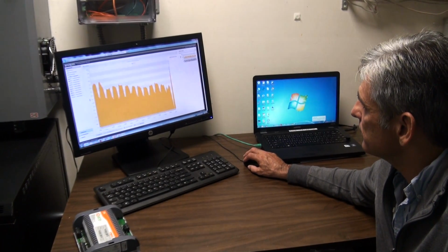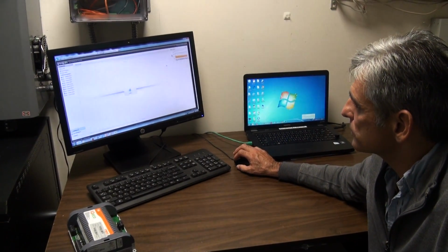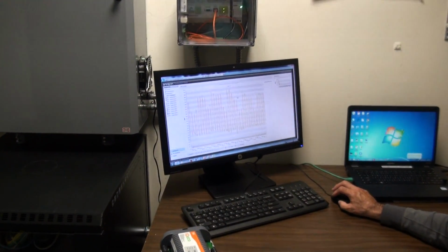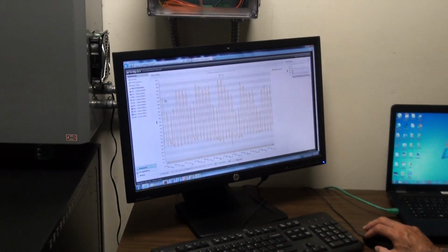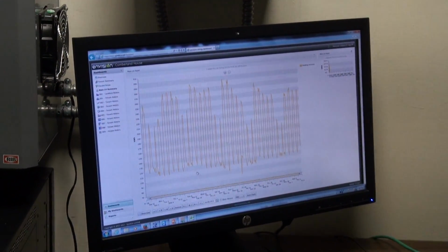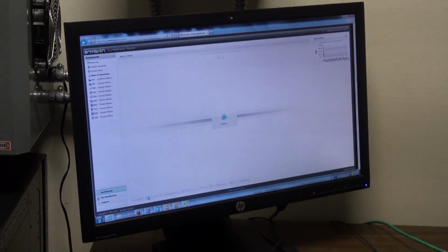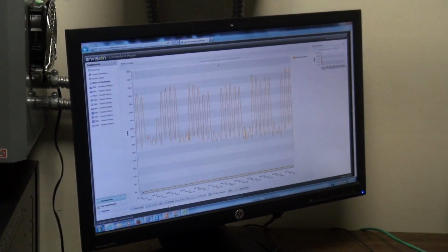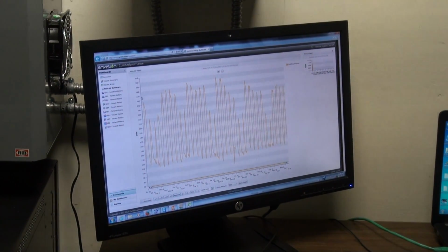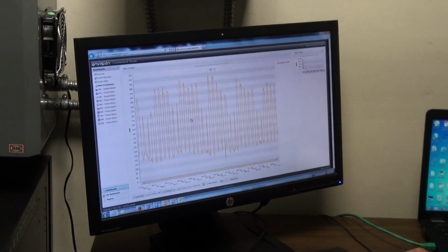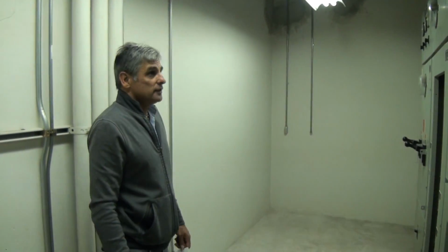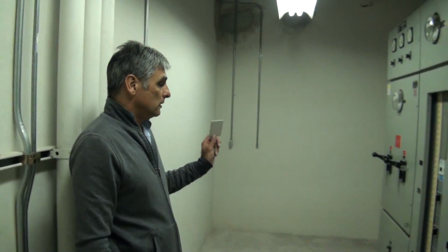And we can do this in many ways. You know, we can look at the panels, we can represent as a typical graphical usage. So again, you can see what your building is using. And again, we can go back a year. Again, we were in the 350s, and now if we go back to today, to current, we're averaging 270s, 260s. You know, we've saved a tremendous amount of energy in this building. This is the main distribution plant, 4,000 amps.